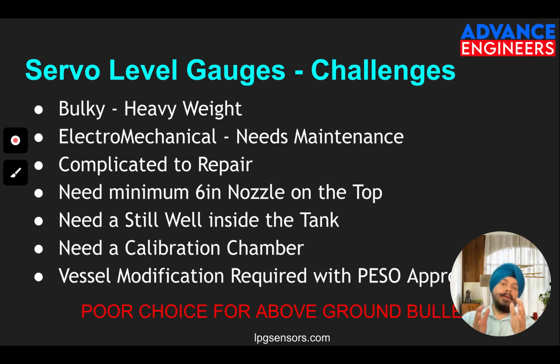Now, all technologies apart, it needs one nozzle from the top so that the float goes inside. It's the minimum requirement, because unless you have a nozzle on the top, you will not be able to bring in the float. Now, this float is also hanging on a very small, very thin wire. That wire also snaps sometimes, because it's LPG, you are blind on it. So during a maintenance procedure, you give a command to the servo gauge to pull the float up to the top. And when you pull the float to the top, it's not guaranteed that the float has reached the top. Sometimes it gets stuck in between in the wall or somewhere in the chamber itself.